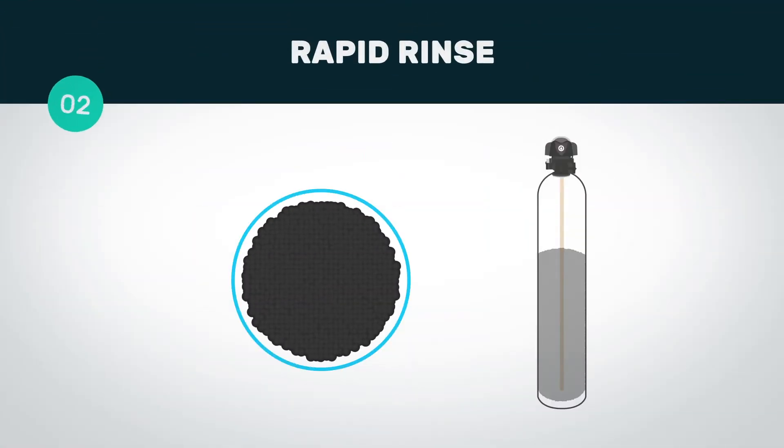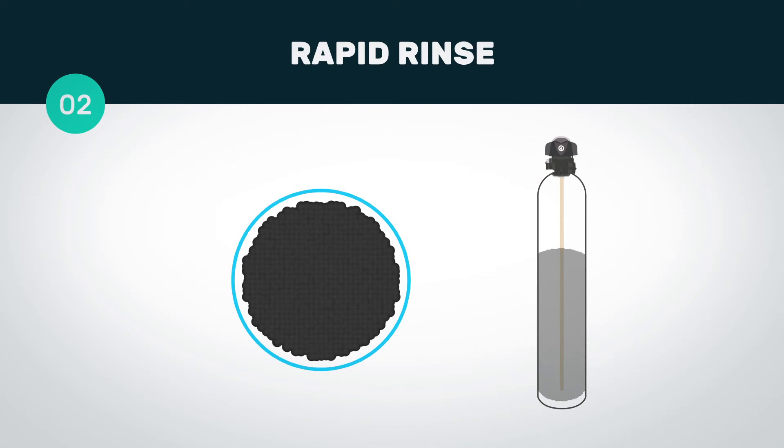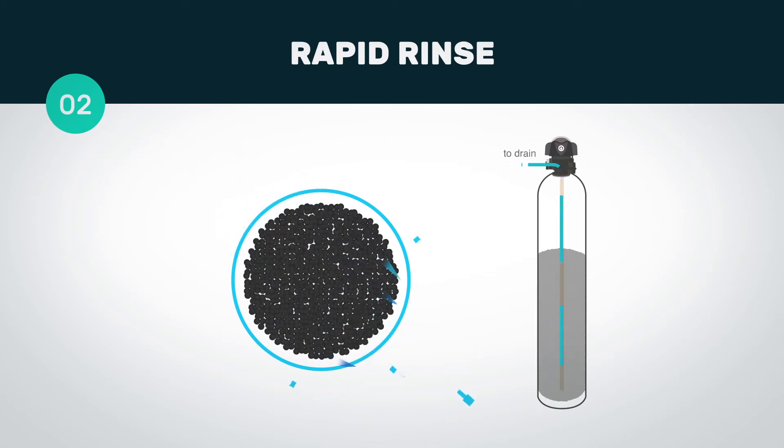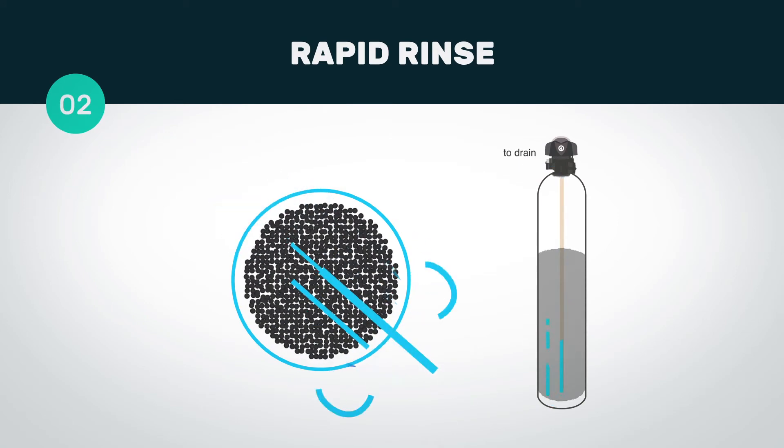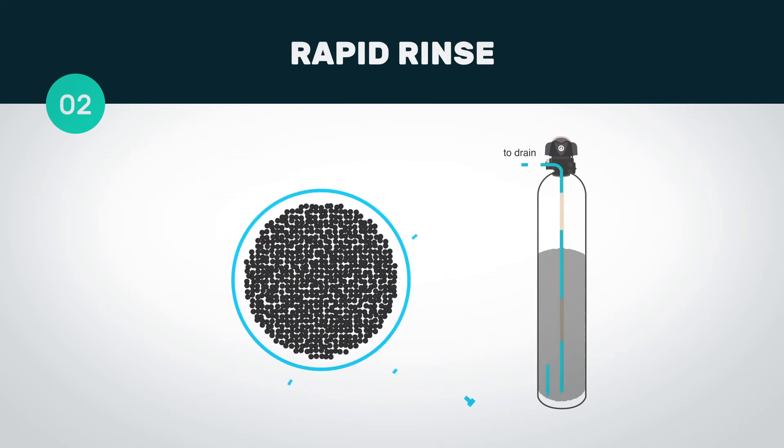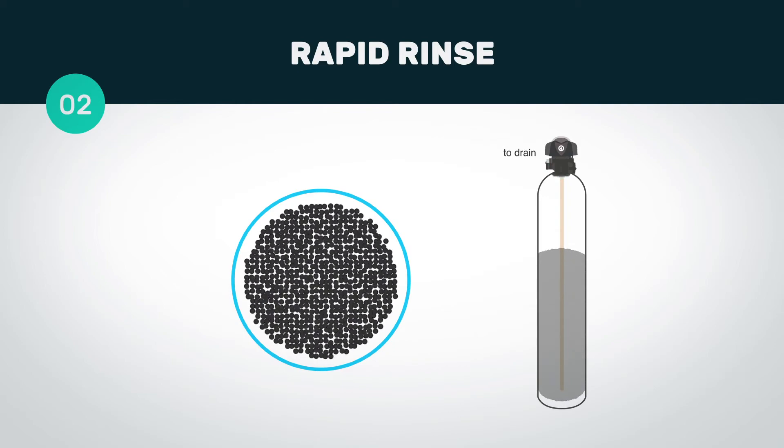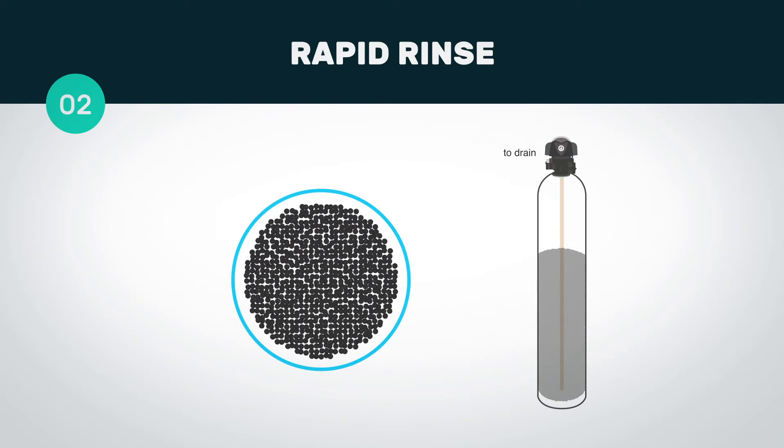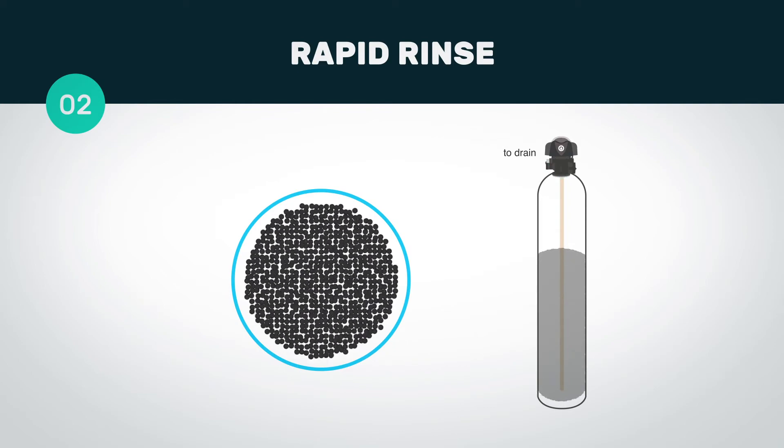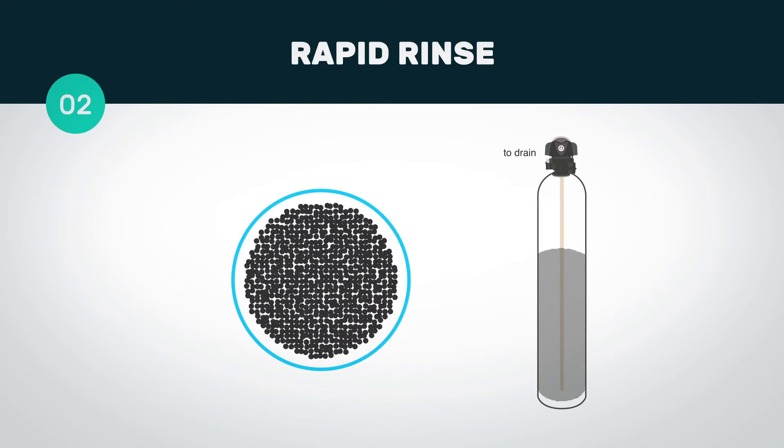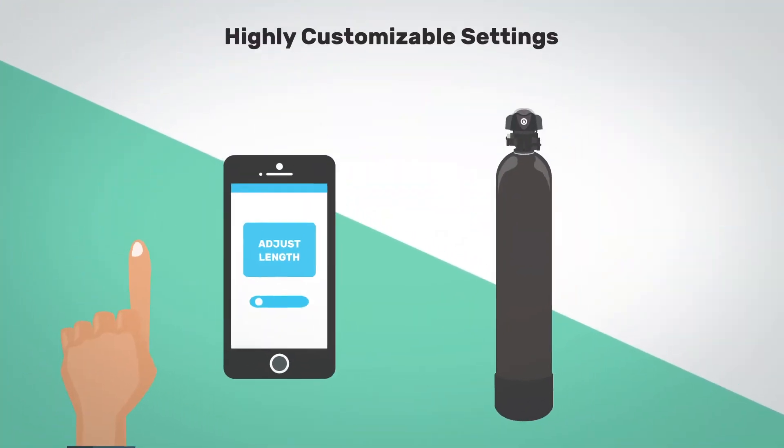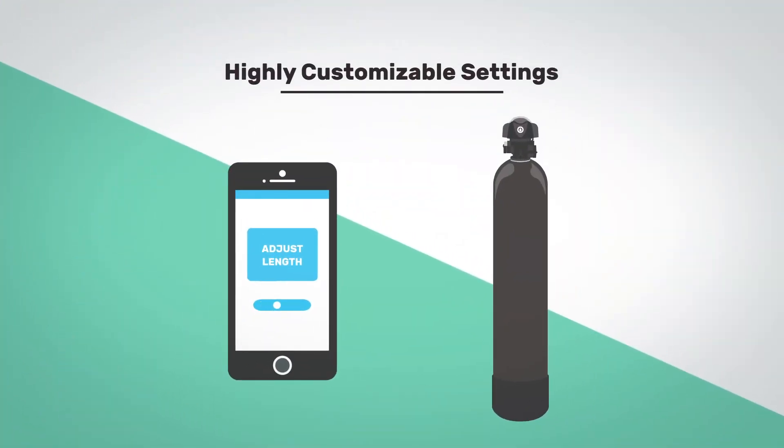Once the backwashing cycle has been completed, the filter begins a rinse cycle, where the water flows down through the media, rinsing and repacking the bed. It then flows up the riser tube and down the drain. This ensures that the filter is ready to return to service. The drop app allows you to adjust the length of both of these steps and also allows you to initiate a cycle manually if desired.